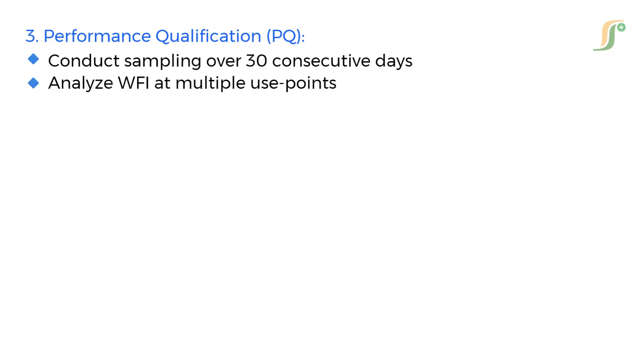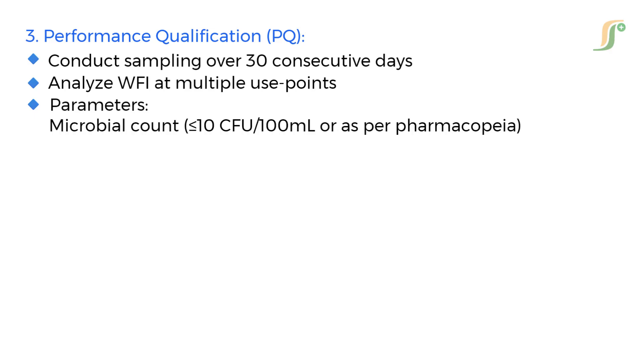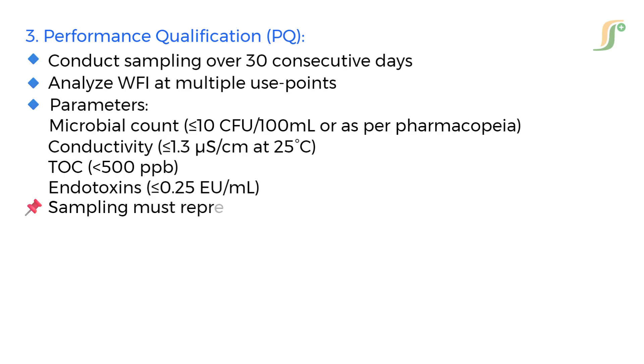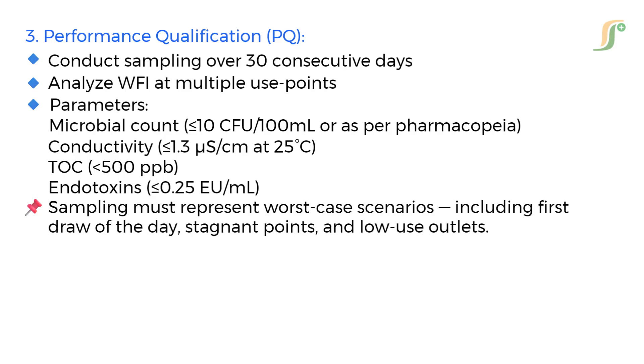Third, Performance Qualification: conduct sampling over 30 consecutive days and analyze WFI at multiple use points. Parameters to verify during PQ include: microbial count — less than 10 CFU per 100 ml or as per pharmacopoeia; conductivity — less than 1.3 microsiemens per centimeter at 25°C; TOC — less than 500 ppb; and endotoxins — less than 0.25 EU per ml. Sampling must represent worst-case scenarios, including first draw of the day, stagnant points, and low-use outlets.